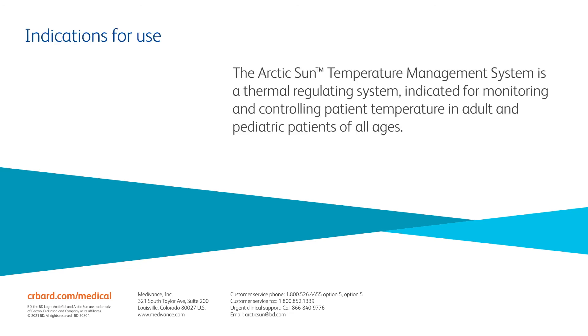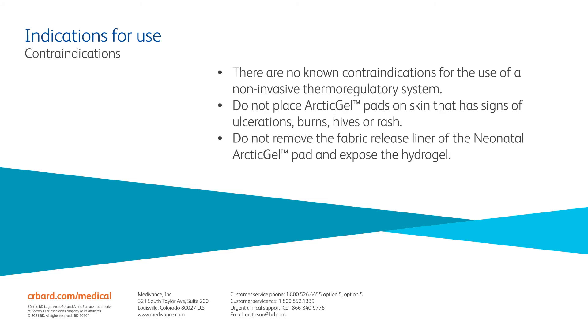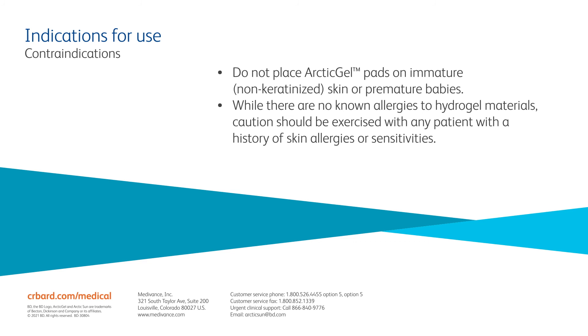The Arctic Sun Temperature Management System is a thermal regulating system indicated for monitoring and controlling patient temperature in adult and pediatric patients of all ages. There are no known contraindications for the use of a non-invasive thermoregulatory system. Do not place Arctic gel pads on skin that has signs of ulceration, burns, hives, or rash. Do not remove the fabric release liner of the neonatal Arctic gel pad and expose the hydrogel. Do not place Arctic gel pads on immature, non-keratinized skin or premature babies. While there are no known allergies to hydrogel materials, caution should be exercised with any patient with a history of skin allergies or sensitivities.